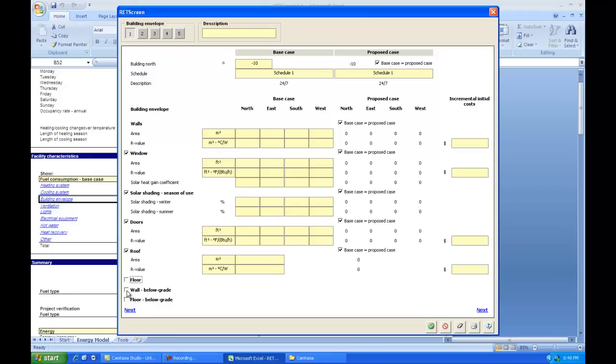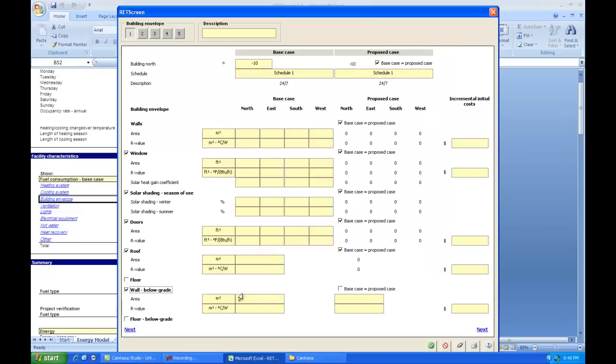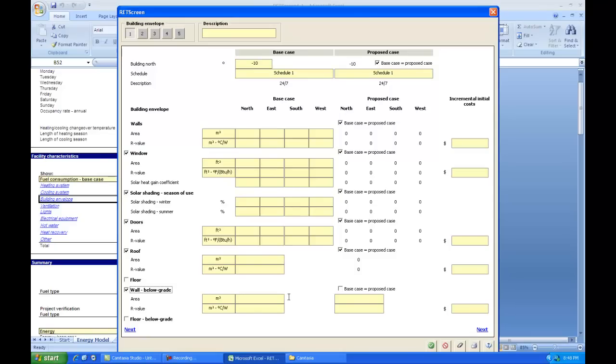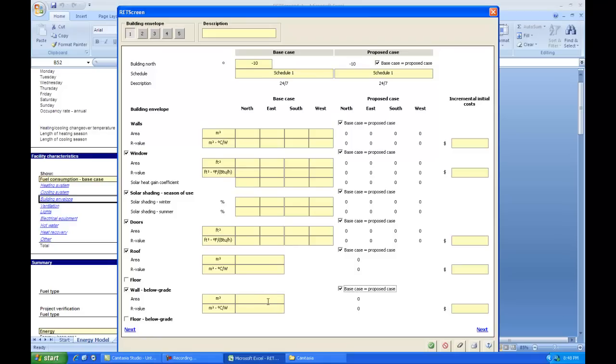We will likely have wall below grade and floor below grade. So the wall below grade is the foundation of the house, at least the part of it that is below grade. Again, we have the area and the R value to enter here. And again, the direction that it faces doesn't matter. We've only got one box to put our stuff in. That's because the sun doesn't shine on things that are below grade.